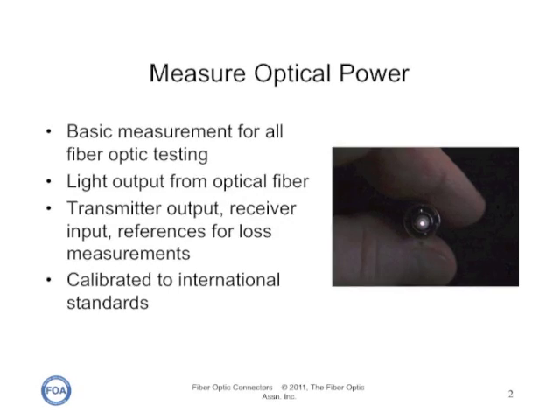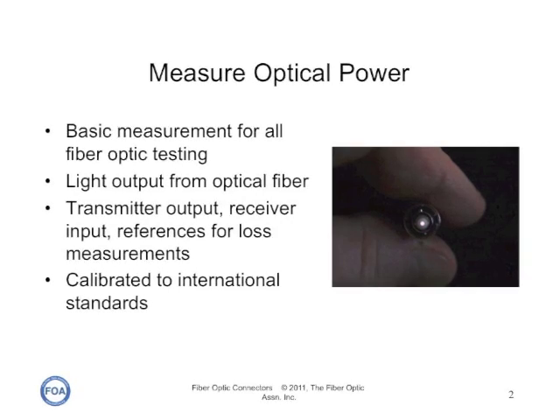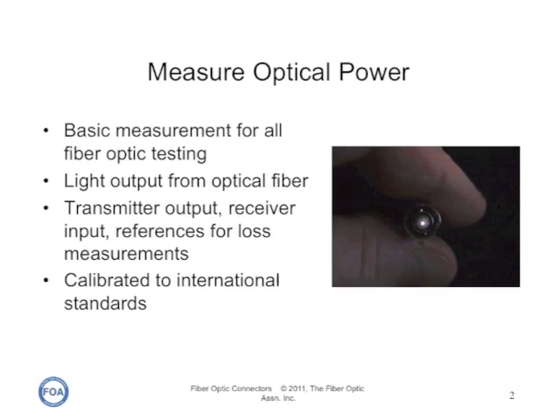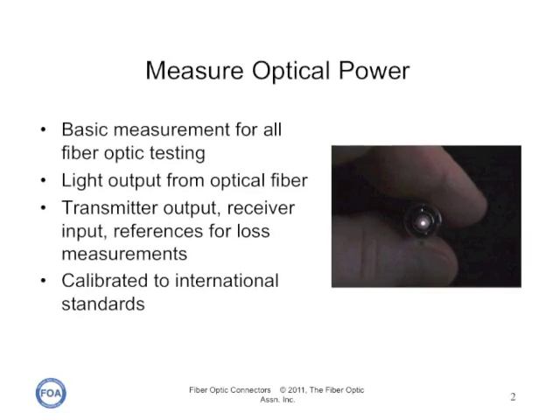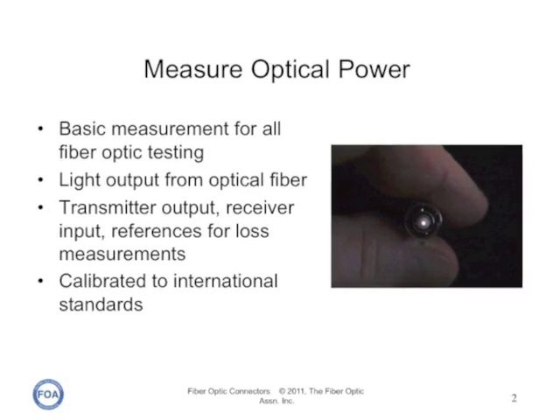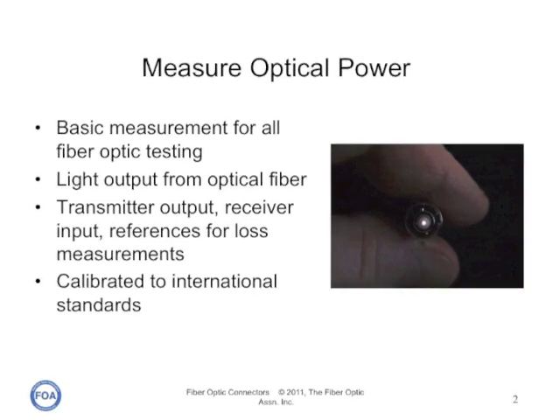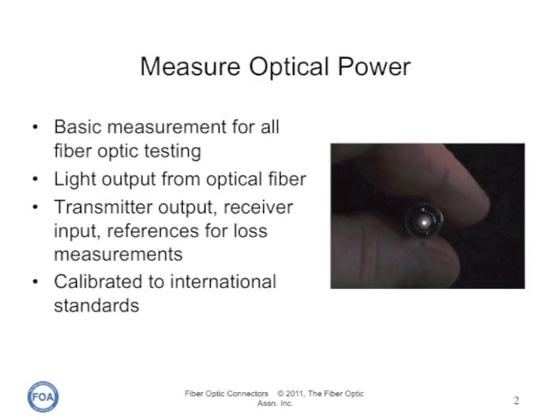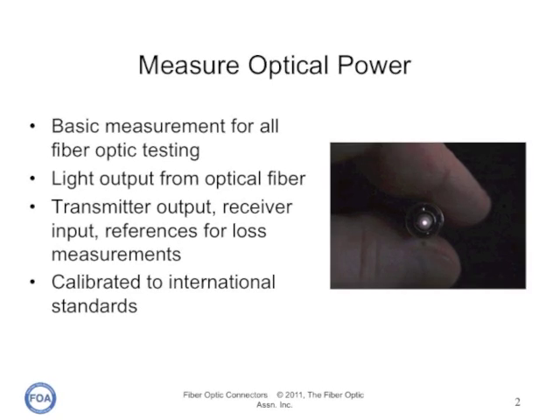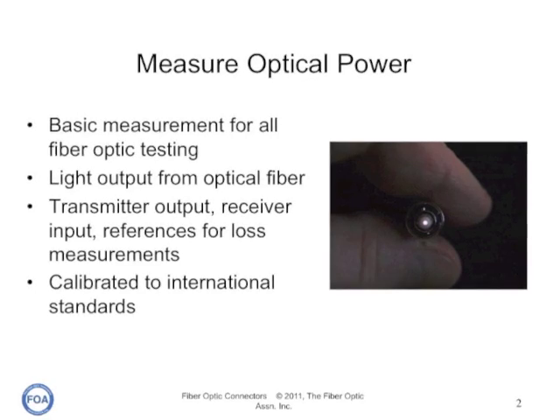Optical power is the basis of most measurements for fiber optic testing. We use it to measure the output of optical fibers so we can determine the output of transmitters or the inputs of receivers. We use it as references for measurements of optical loss, and we use it for calibrating the trace on an optical time domain reflectometer.